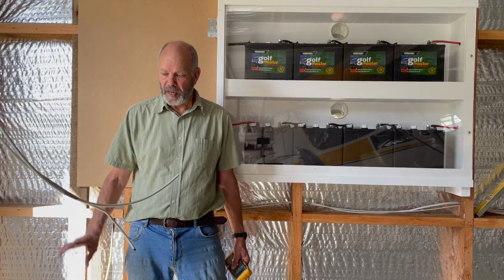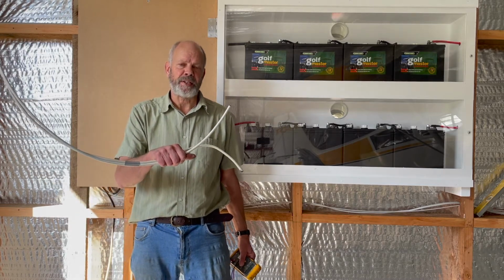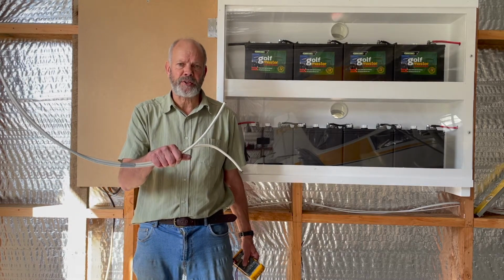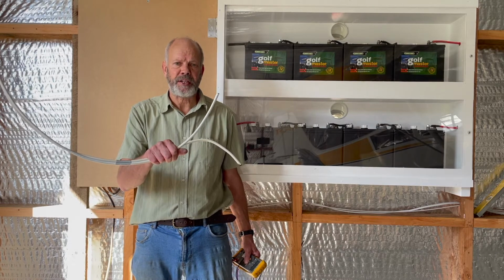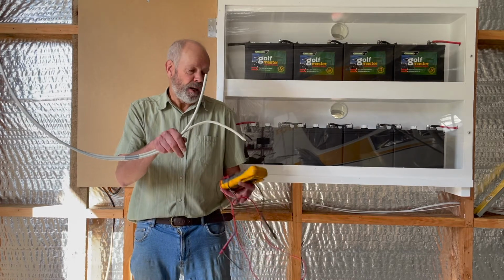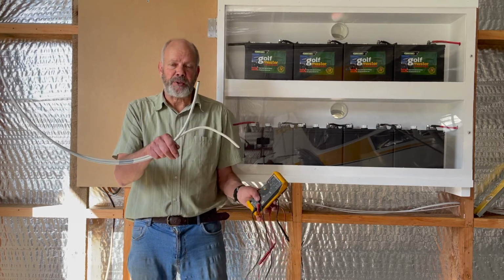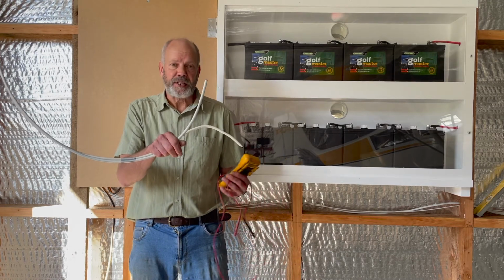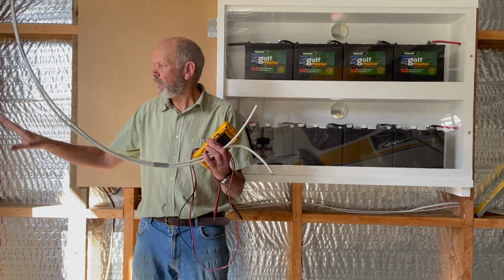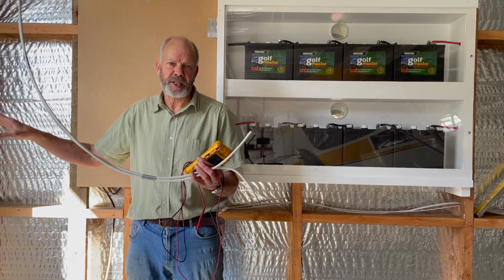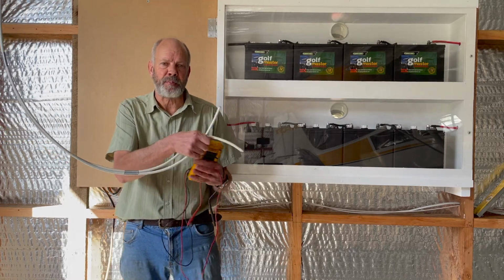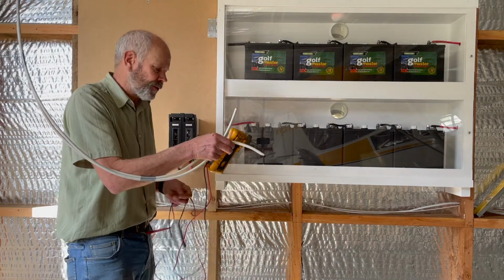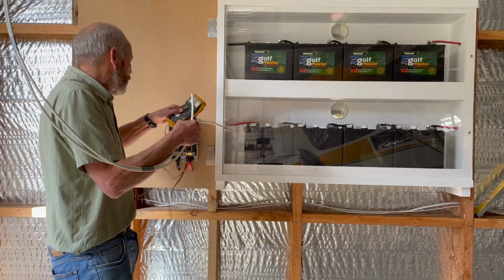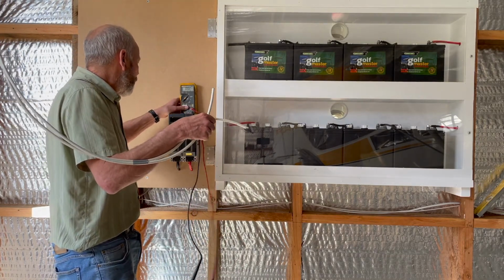Here I am down at the power board. The solar array is completed up on the roof. I've left it turned on so I can demonstrate and also test my leads coming down. I've got my voltmeter set to volts DC. We've looked at the placard on the solar module, and it says we should get around 80 volts as an open circuit voltage. So the first thing I'm going to check is the open circuit voltage of my solar array.